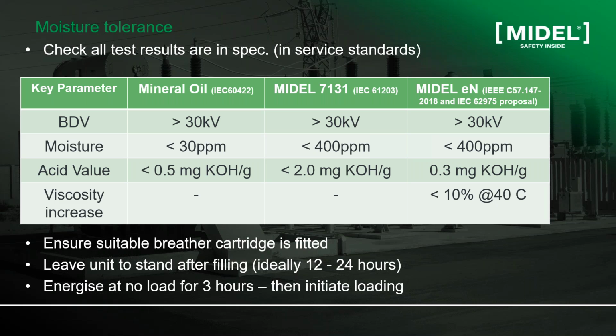Esters have a different story. They can tolerate much higher moisture content without reducing the breakdown voltage, and I will focus on this later. So in this table, the moisture content in service for synthetic and natural esters should not exceed 400 ppm for a retrofilled transformer. And also the acid value, as you can see, mineral oil has different limits from esters. I want to focus here on viscosity. For mineral oil and synthetic ester, we don't expect any viscosity increase as they age because they are oxidation stable. For natural esters, you may observe an increase in viscosity, and if this increase becomes more than 10%, then you need to take action because you have severe oxidation processes happening.